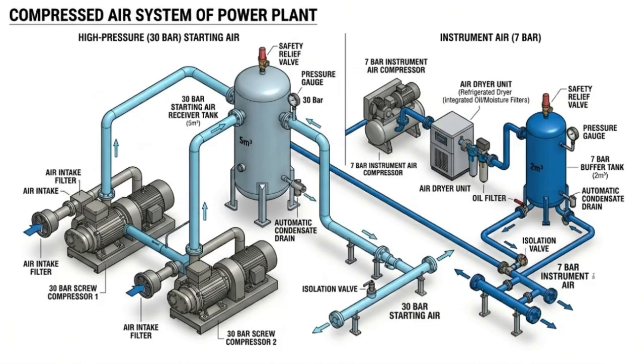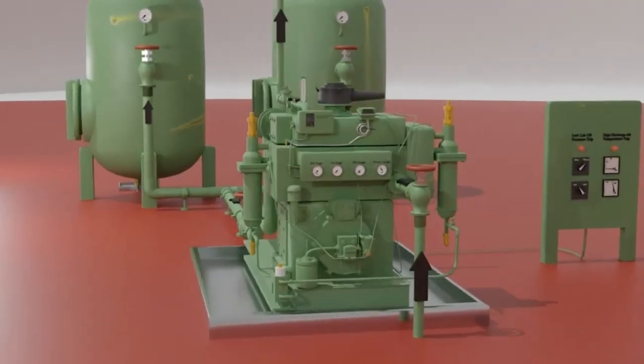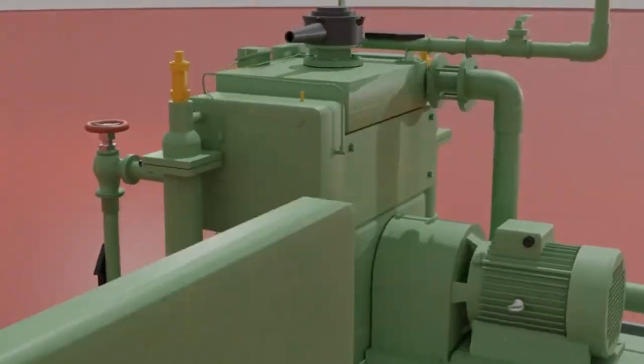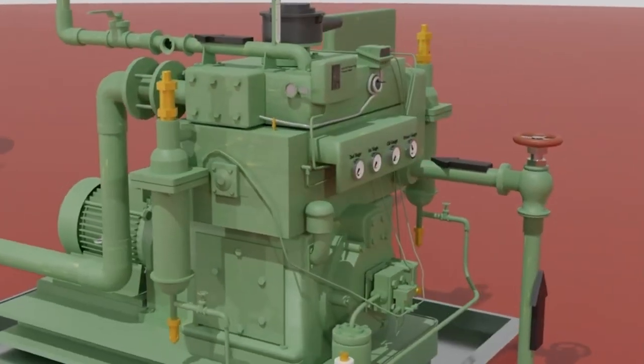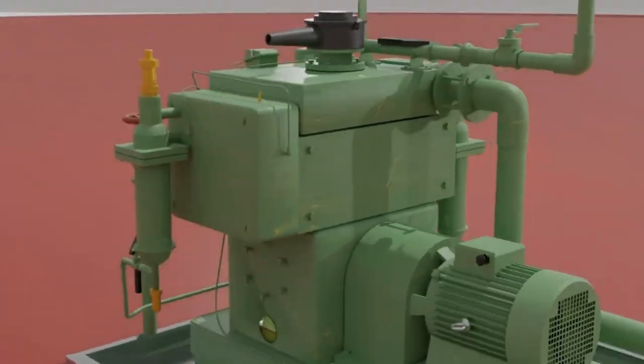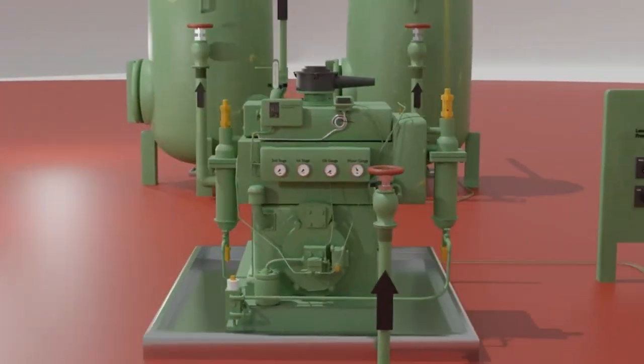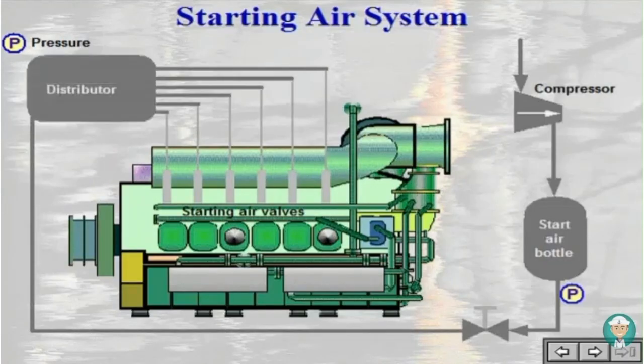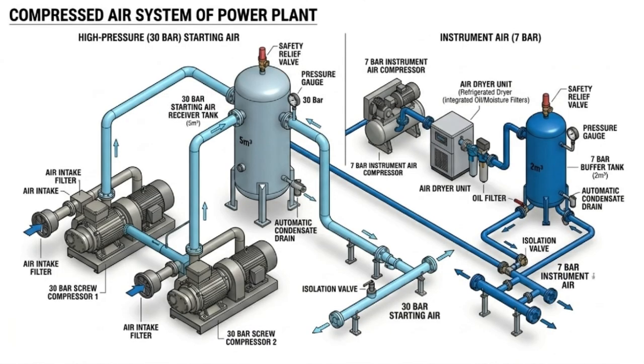The compressed air system supports two critical functions within the power plant: engine starting and pneumatic control. High-pressure air compressors charge the air receivers to provide starting air for the engine. During startup, this compressed air is injected into the cylinders to rotate the crankshaft until the engine reaches firing speed. A separate branch supplies clean and dry instrument air for pneumatic valves, actuators, and safety control systems across the plant.